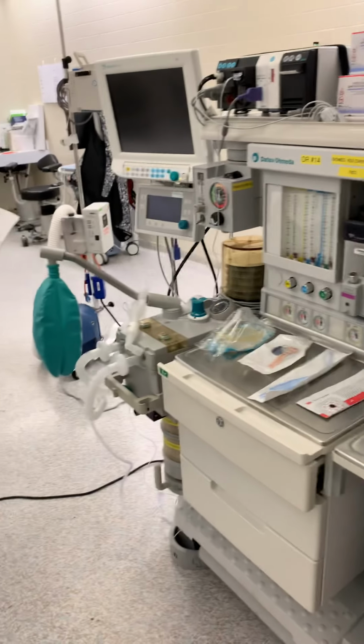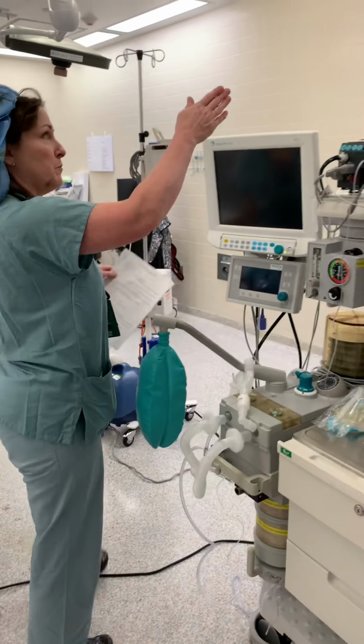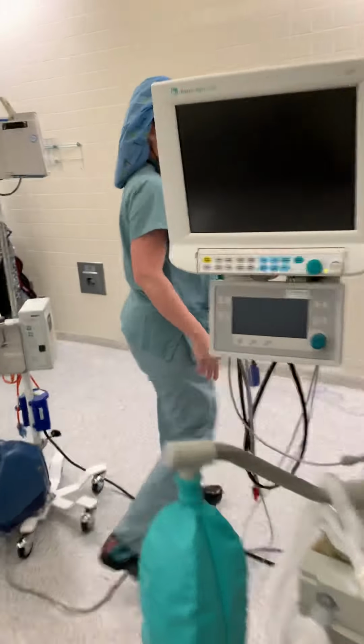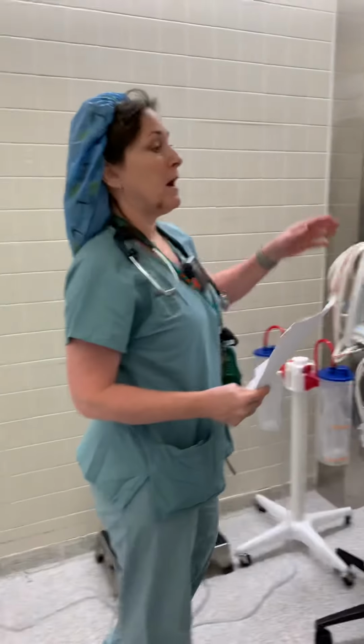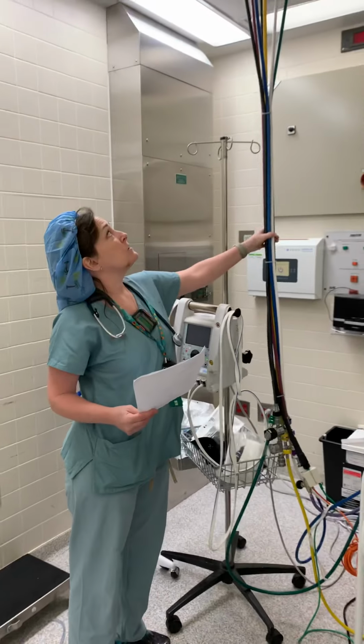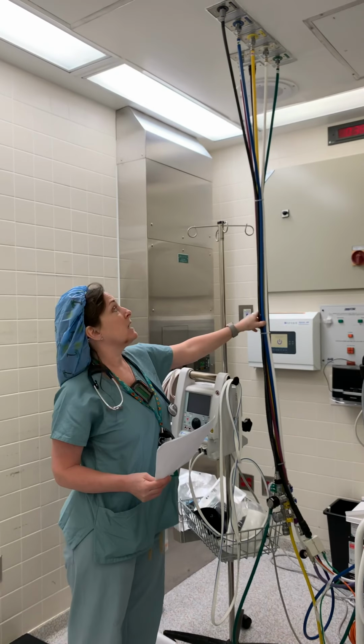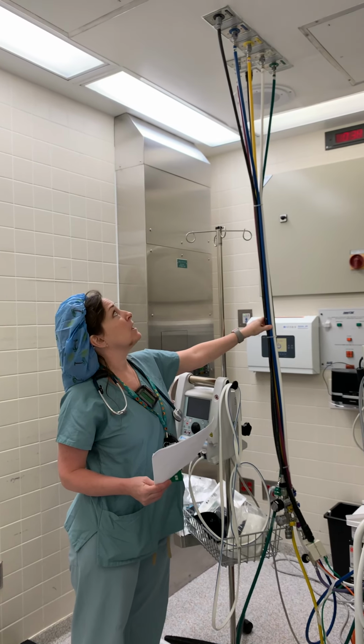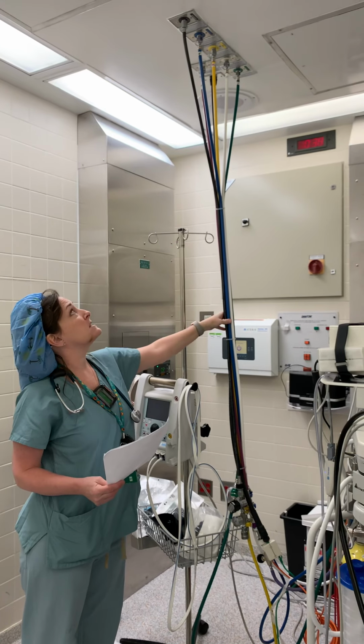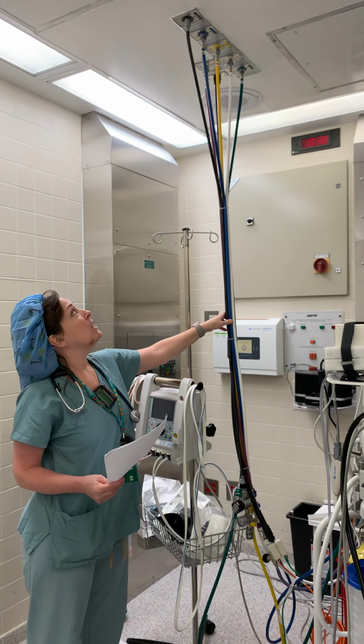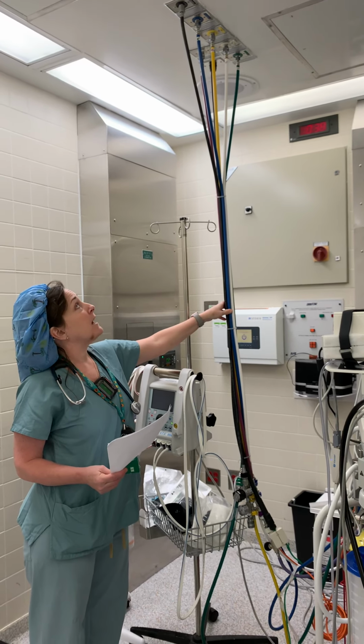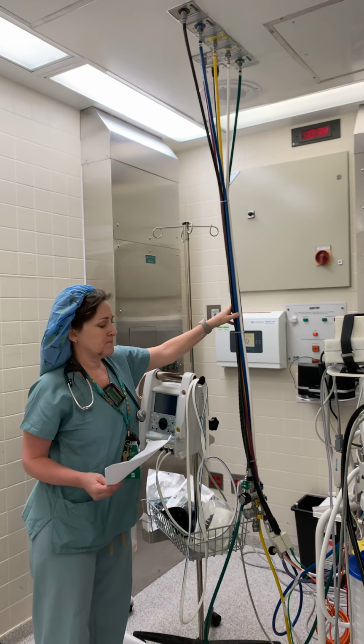What we're going to first have to do is go back to the back of the machine. This is usually where you're going to find your pipelines. Your pipelines are coming from the ceiling, carrying the different gases that we use. They're color coded. The blue is nitrous, the yellow is air, the purple and the white are vacuum, and the green is oxygen.